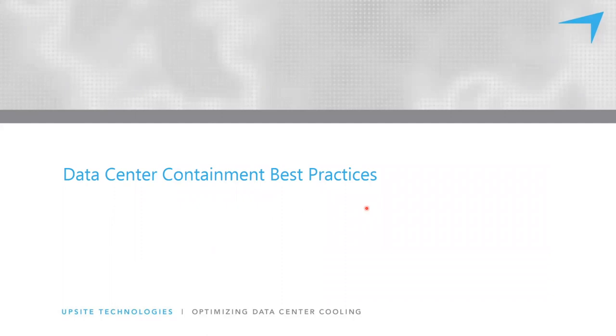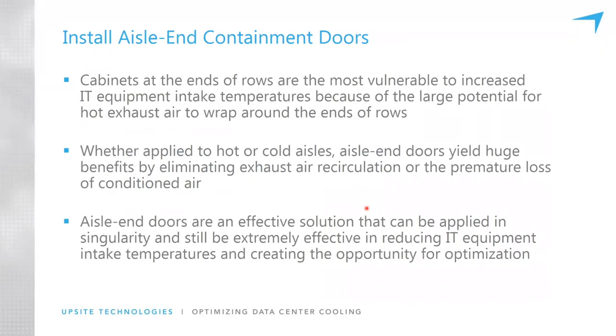So let's start going through some of the best practices. Cabinets at the ends of the row are the most vulnerable to increased IT equipment intake temperatures because it's very easy for that hot air to flow around the ends of the row and cause elevated temperatures in those cabinets. And whether doors are applied to a hot or a cold aisle, they can yield huge benefits. And just doing that alone can really make a big difference.